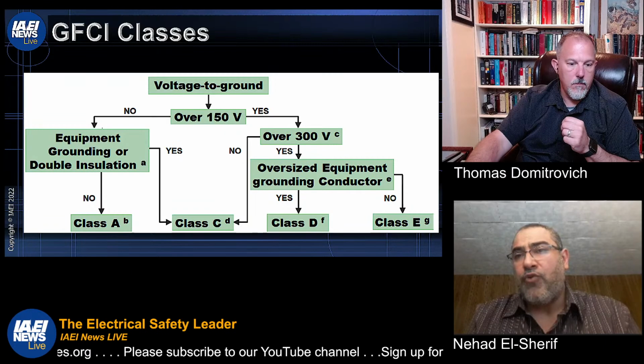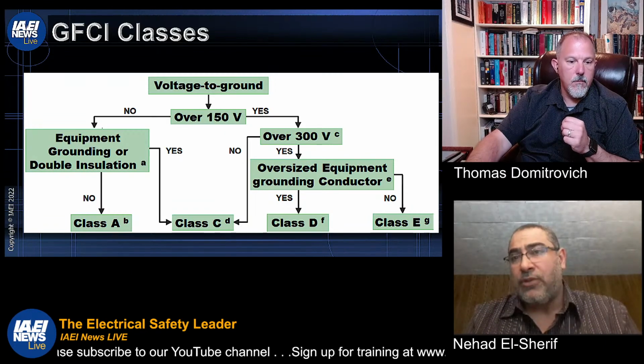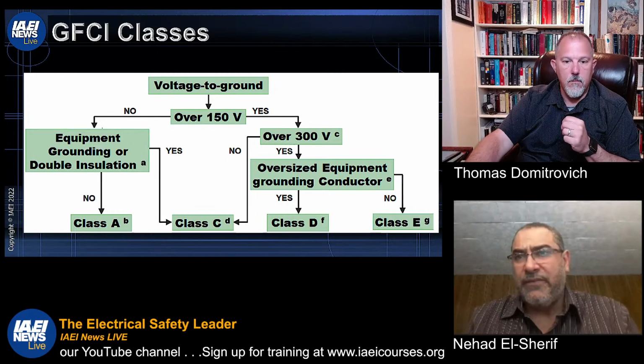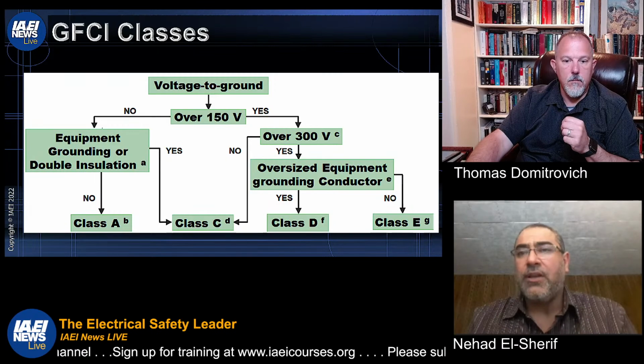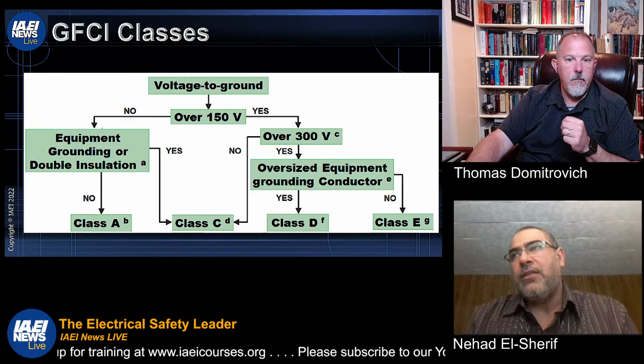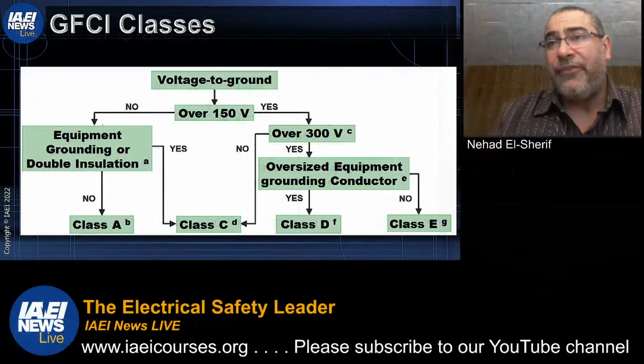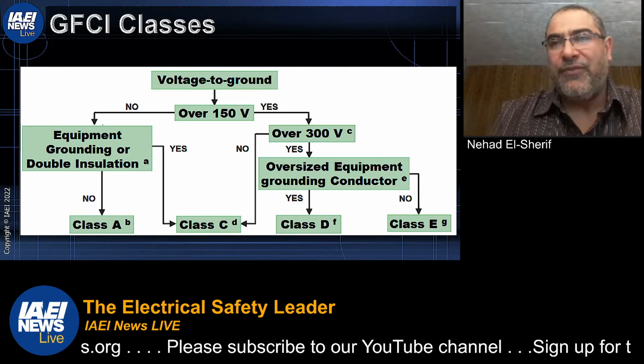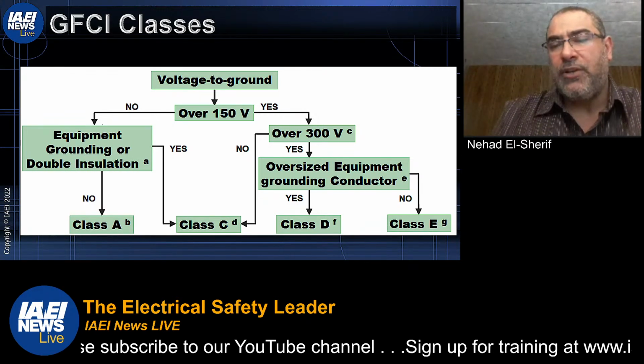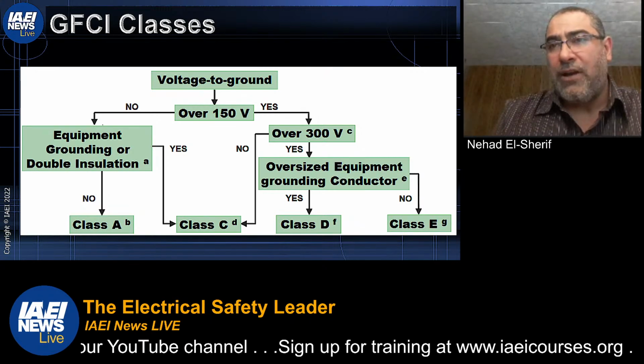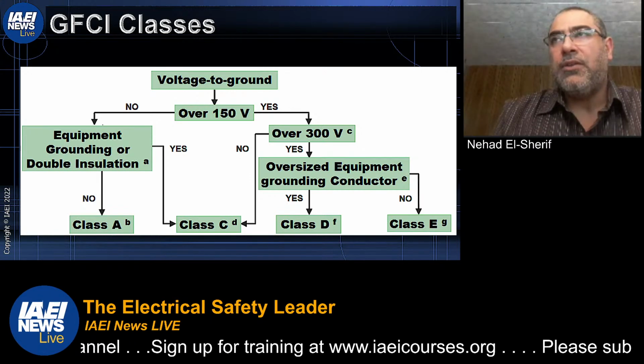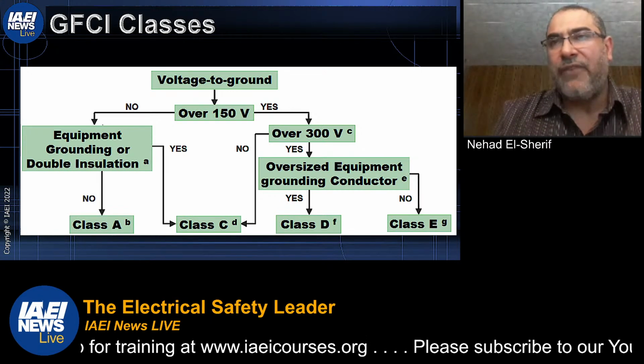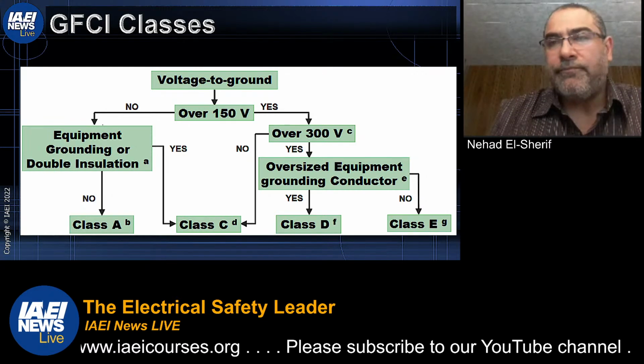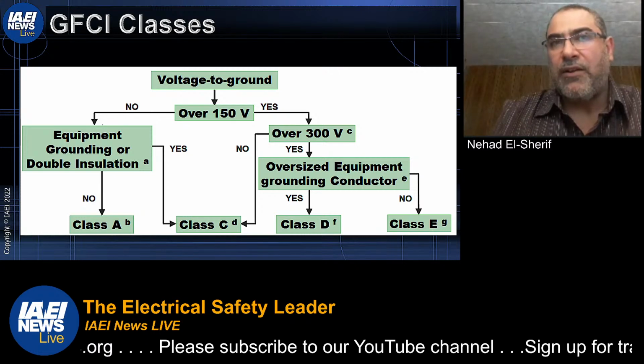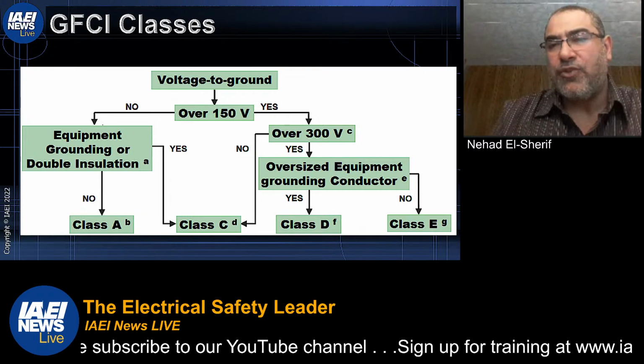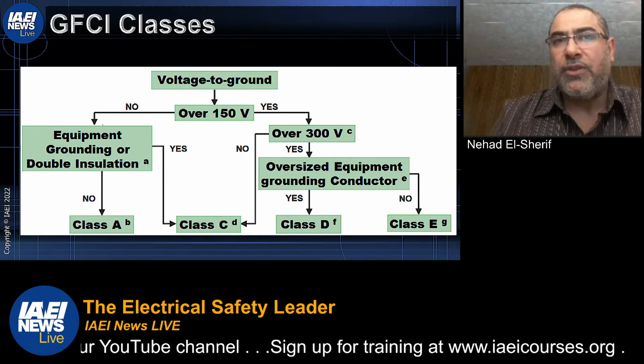The distinction is if your equipment grounding conductor is oversized, and there's an equation in Appendix A, I believe, in the UL 943C that shows you how to oversize your grounding. The point is they oversize the grounding to limit the voltage to ground to 150 volts, which is considered a relatively safer voltage to limit the current going to a person, because the current going through a person would be the voltage to ground divided by the impedance of that person. So 150 volts divided by the impedance, which is roughly, UL uses 500 ohms as a typical value. It's like 500 to 1.5K, but use 500 to be safer. To do the math, this is the amount of current leakage that you'll be allowing to go through the person coming in touch with a faulty piece of equipment.